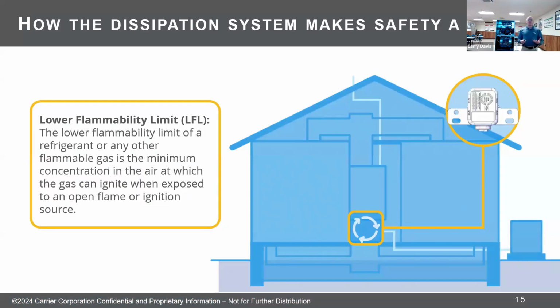But because it falls within that A2L category, it has a lower flammability limit that we have to deal with. That is the bottom of the concentration of refrigerant in the air at which it can ignite. So we have to make sure we deal with that if we measure a level of refrigerant at that LFL. I think the ASHRAE standard is 50%. Our system measures it at 20. We initiate our dissipation system at 20%. You'll see that in coming slides.